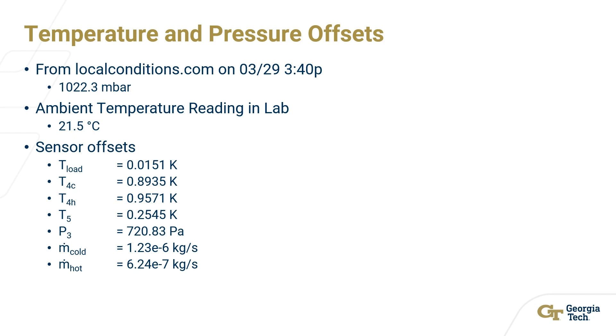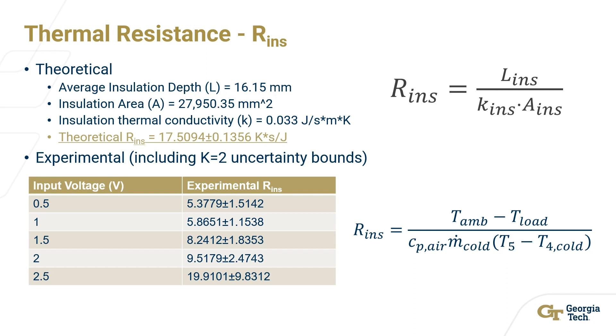After measuring the depth of the insulation device and using the equation in the top right corner, the theoretical thermal resistance was calculated to be 17.5 plus or minus 0.1356. Our experimental values can be seen listed in the table above. The closest experimental value to the theoretical value happened at 2.5 volts. Mostly the theoretical value was higher than the experimental, likely due to the depth of the insulation surrounding the load not being the same and it not being fully insulated on all sides.